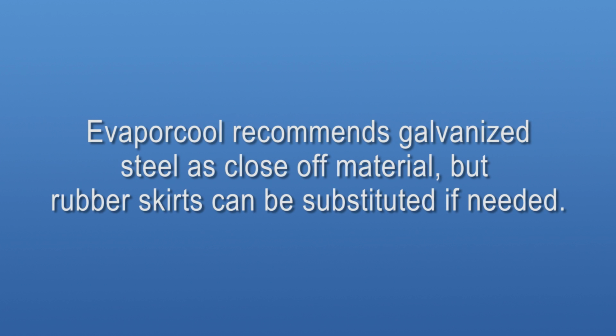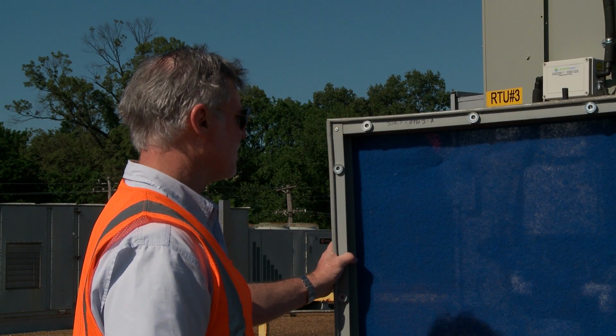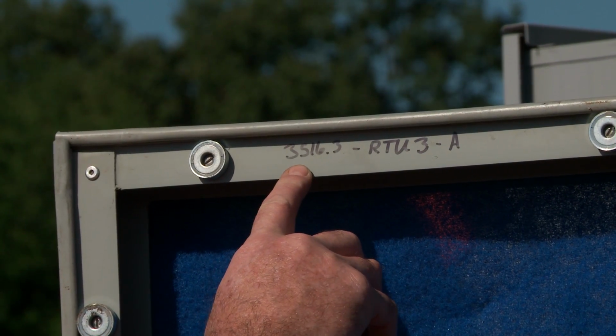Evaporcool recommends galvanized steel of sufficient gauge thickness as close-off material. Sometimes sheet metal is not used, and other specified material like rubber skirts can be substituted. Evaporcool can make recommendations based on your particular install. After the close-off material has been installed, it's now time for the easy frames to be attached to the unit. Each frame is numbered on the top left corner on the back of the frame at the factory and identified on the Evaporcool system layout diagram. The Evaporcool system layout diagram must be followed for proper installation.